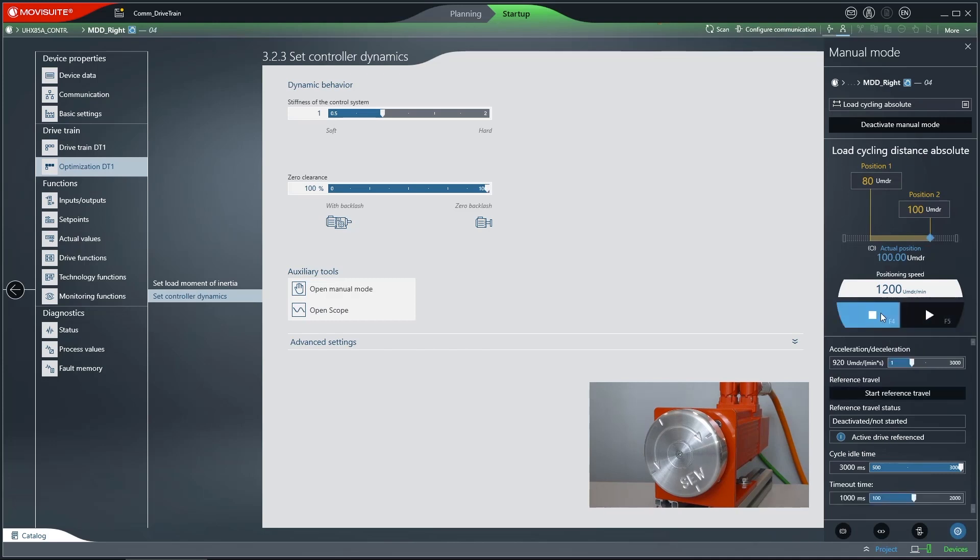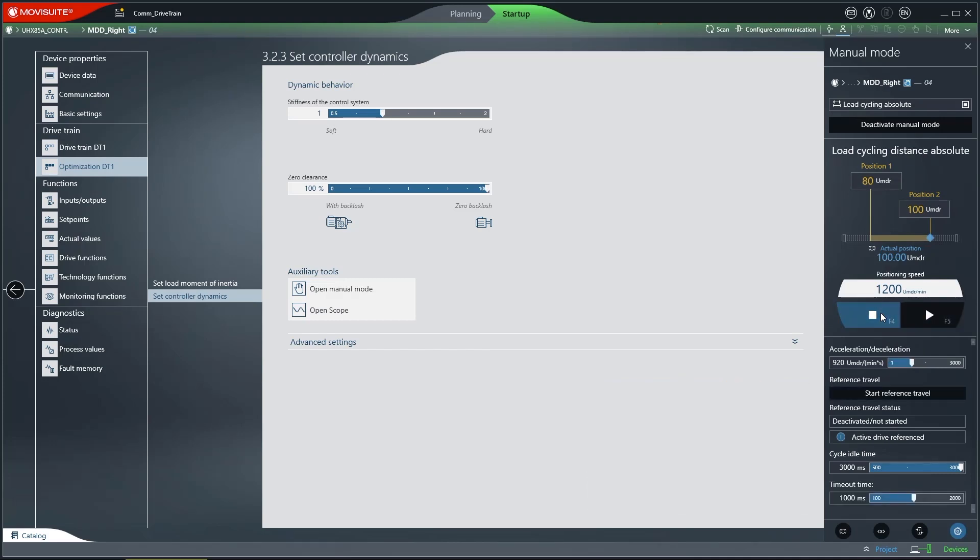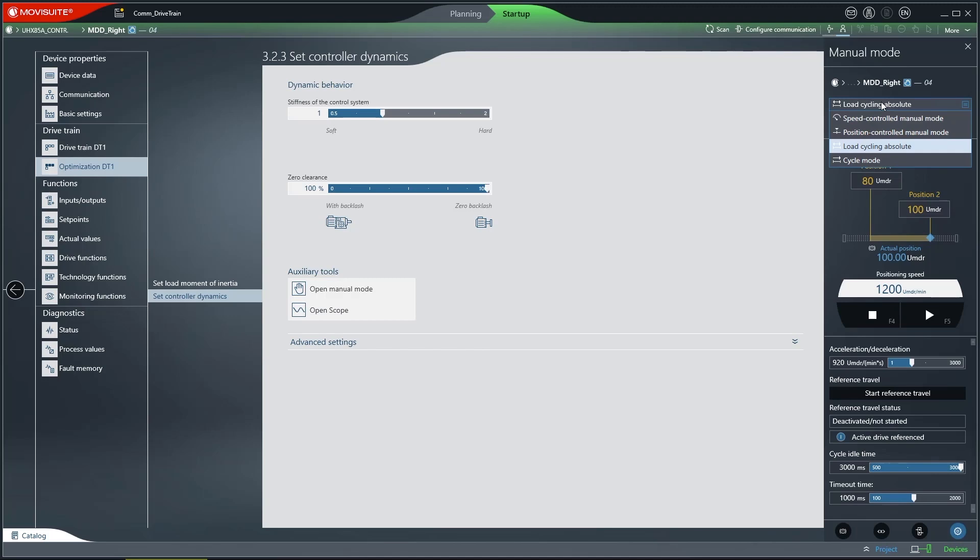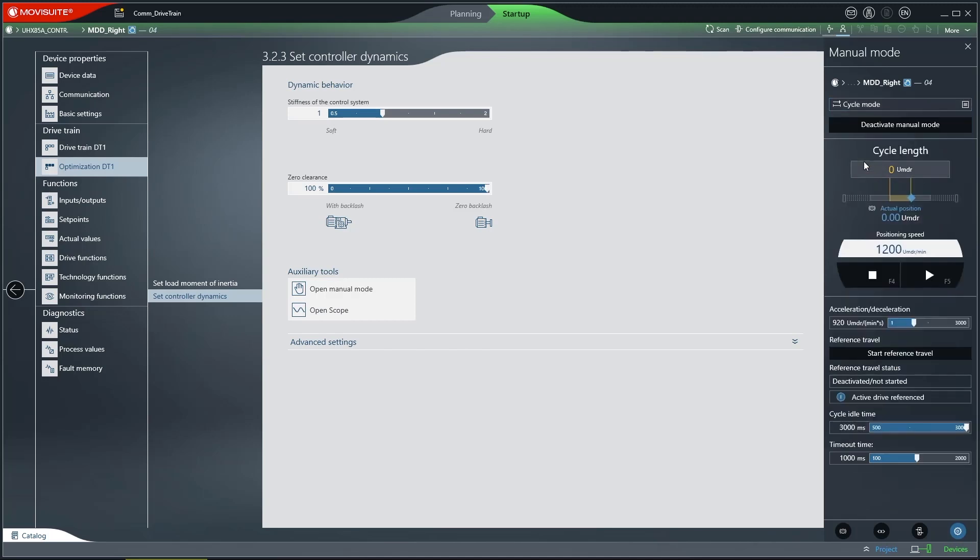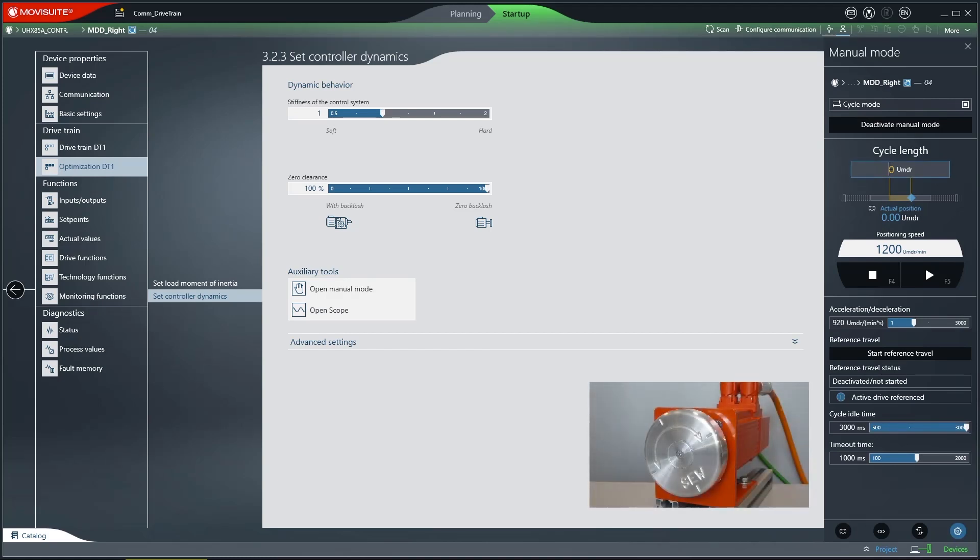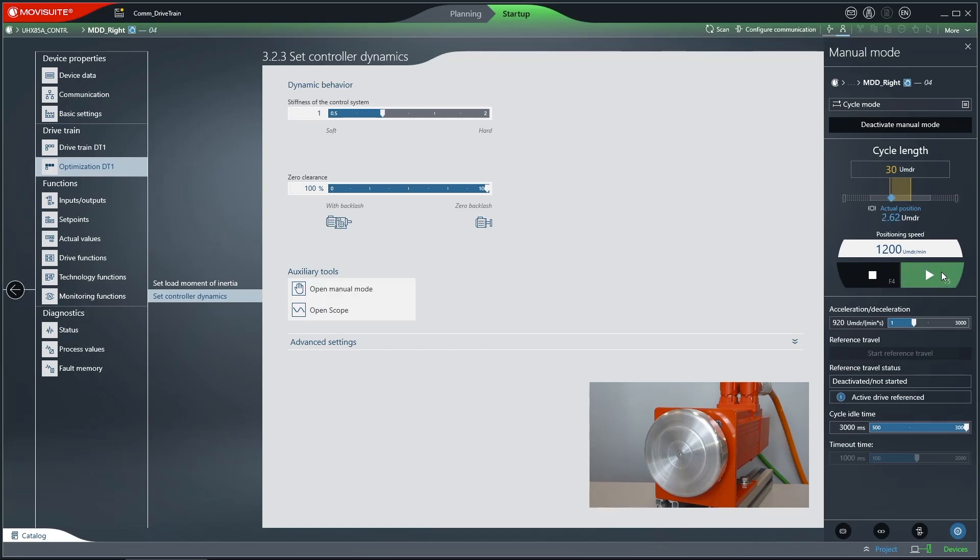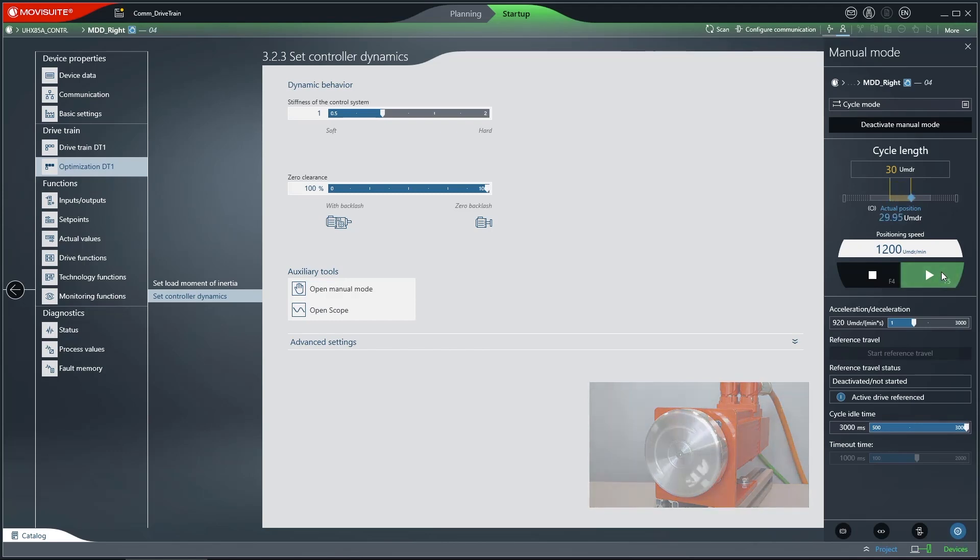If the direction of rotation cannot be changed due to mechanical reasons, for example, you can use the cycle mode as an alternative to load cycling. In this process, the drive travels a previously configured cycle length, and the cycles are interrupted by the cycle pause. A relative actual position is displayed. You can reverse the direction of rotation by reversing the sign in the cycle length field.